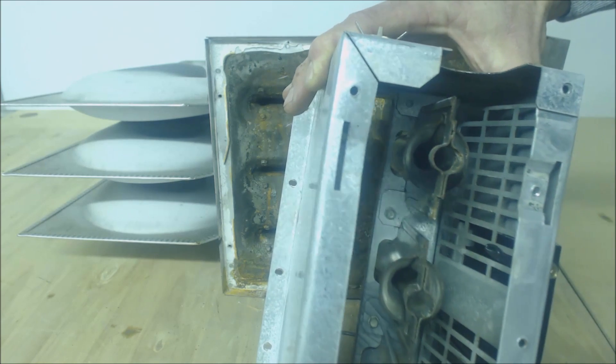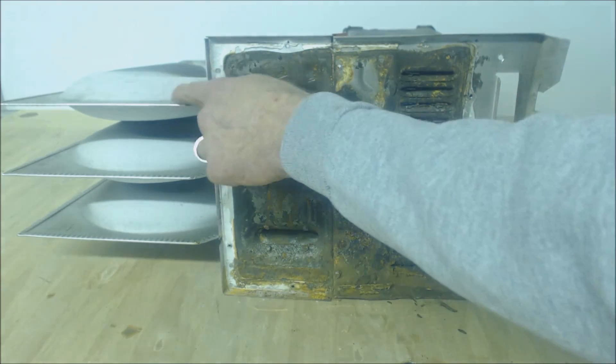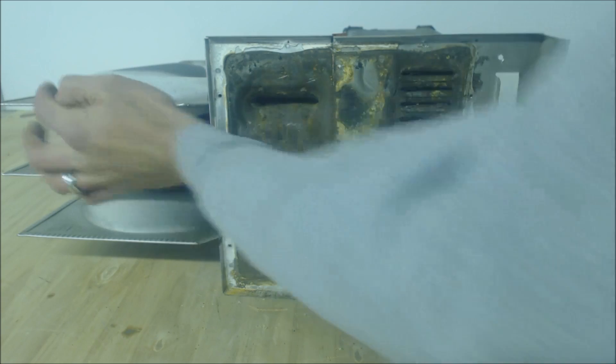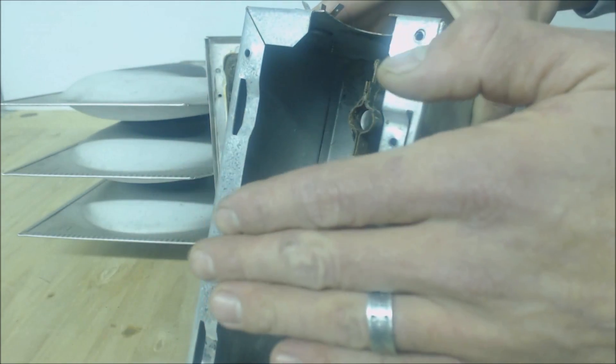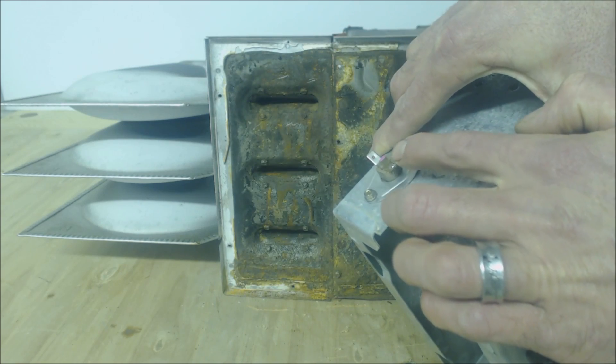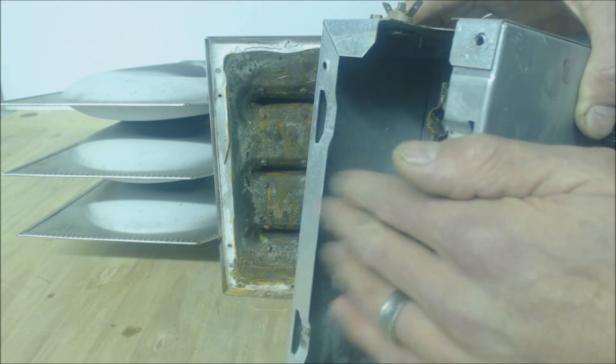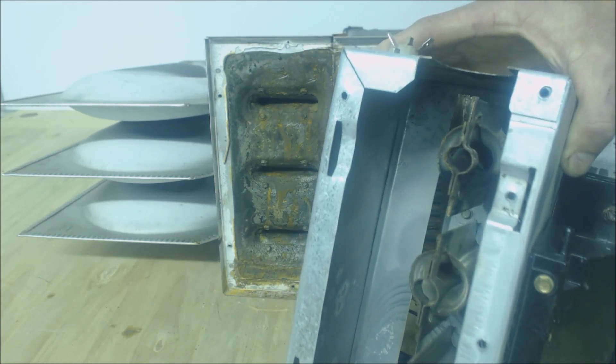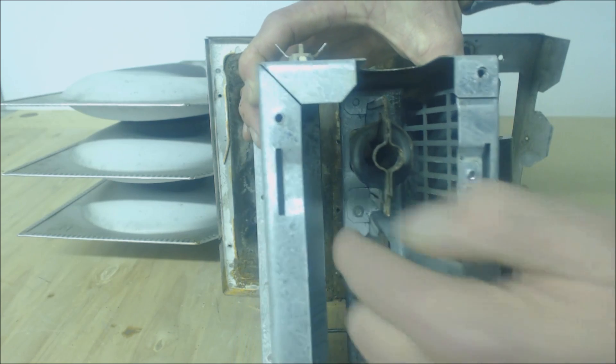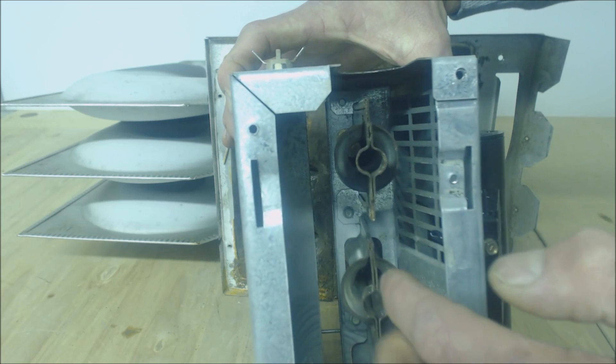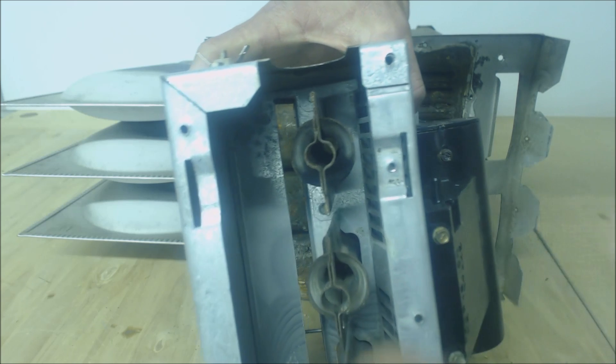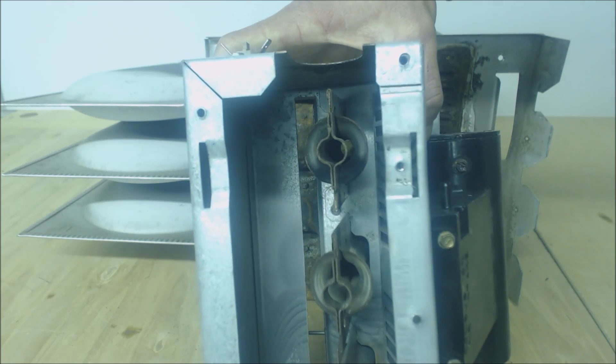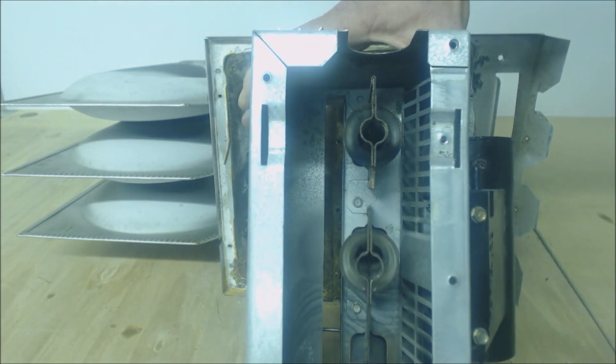That would make everything look fine in the burner box as far as the flames go - nice blue flame - but then when the blower motor turns on, it pushes air across this coil. While it does that, it goes in through the crack and blows back out this way, and that would make this flame roll-out switch pop because you'd have a flame popping a little bit. In the case of a clog heat exchanger, you want to make sure that you have a good path that flame is going in - the same amount on all three, or all four, or all five. You can check your combustion analysis. These furnaces are basically preset.